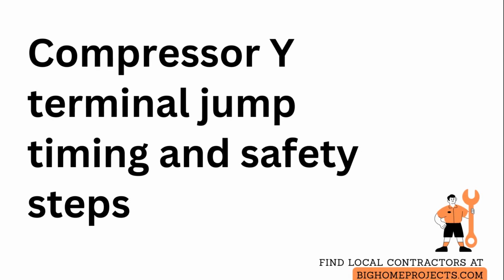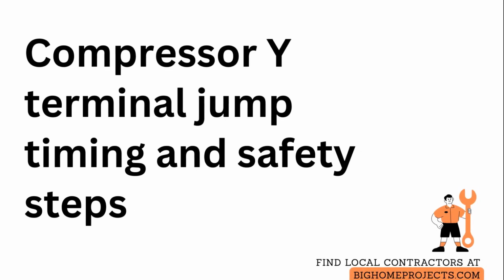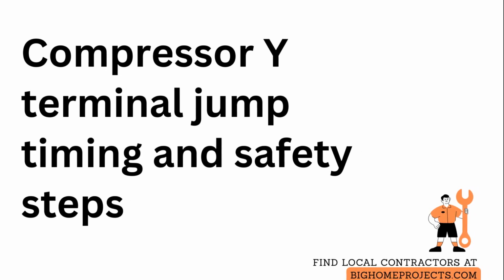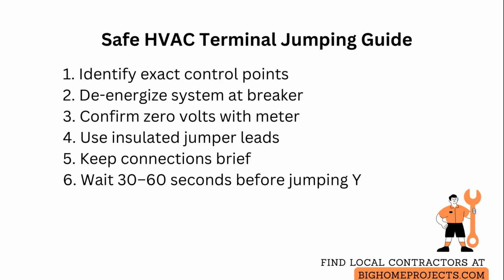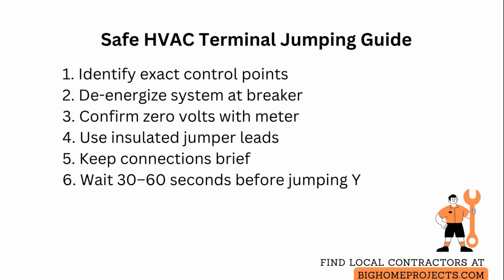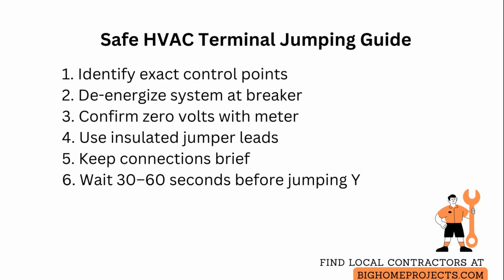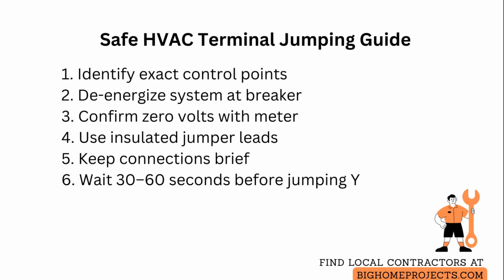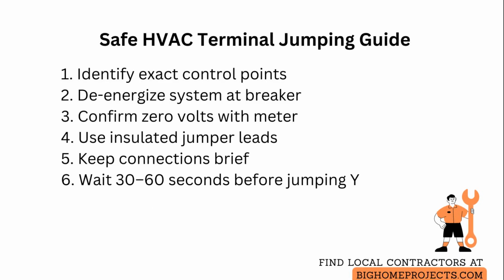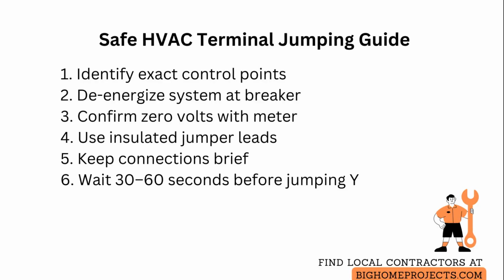Are there situations where jumping terminals could harm the heating, ventilation, and air conditioning system? Jumping control terminals is sometimes used to troubleshoot and temporarily operate components, but it requires precise timing, correct terminal selection, and an awareness of control logic to avoid damage. Always confirm the schematic or wiring diagram first, so you know which terminals are simply control inputs and which are part of interlock or safety circuits.